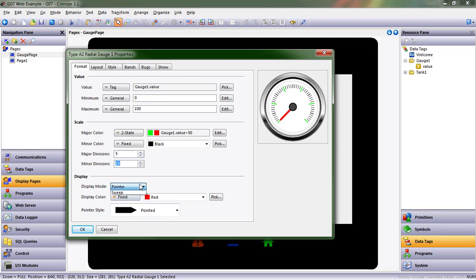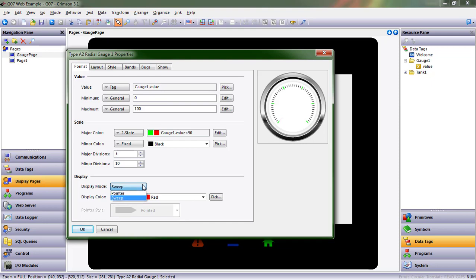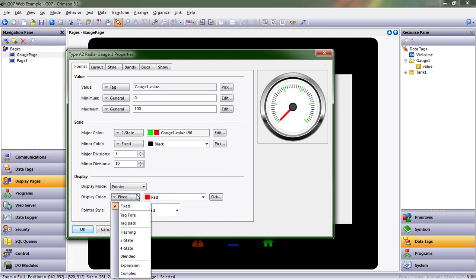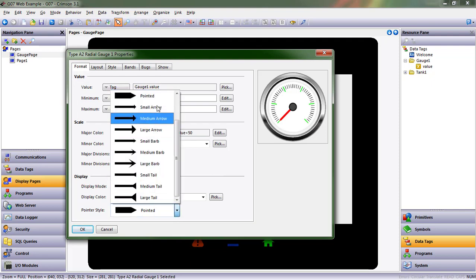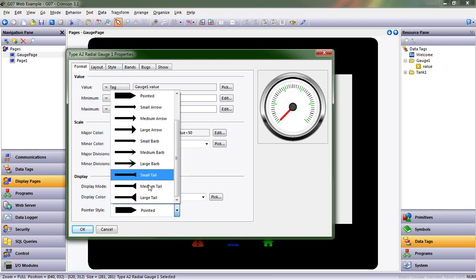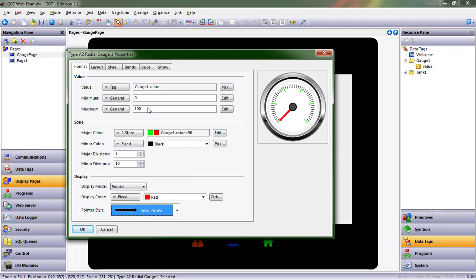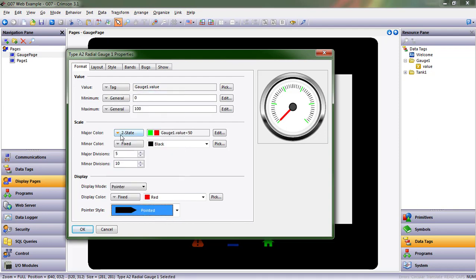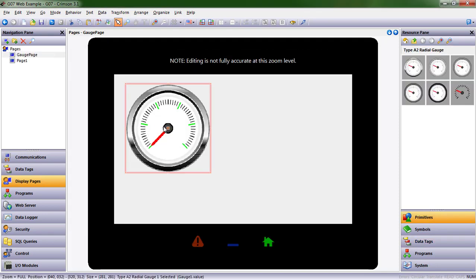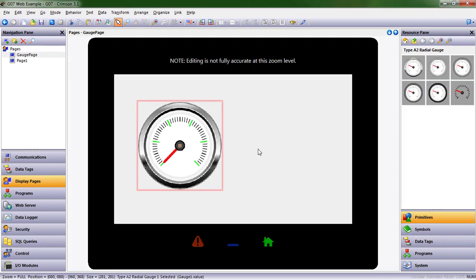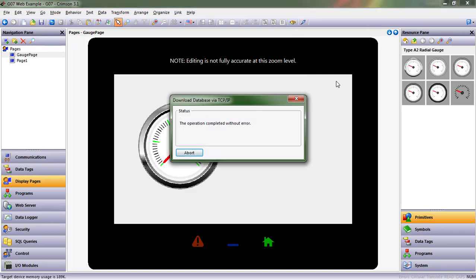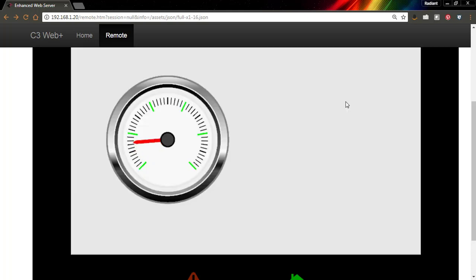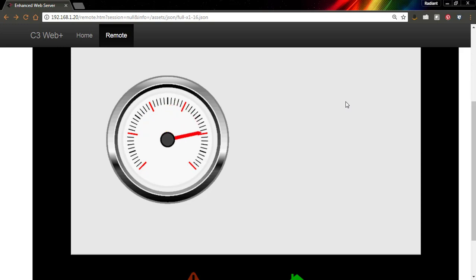OK, we can change the pointer. We can make it a pointer or we can make it a sweep. The sweep will give us a bright red line sweeping around the gauge. We'll look at that in a second. And we can change this pointer as well to change color in any variety of ways depending on what's going on. And then we have a variety of different styles here as well. So maybe I choose a small arrow. I think I like the pointed the best. OK, let's see what this looks like on our HMI. I'm going to go ahead and send it down. And we'll see it in a moment. And as soon as we hit that halfway point, we should see those majors turn. And they did, just like we expected.